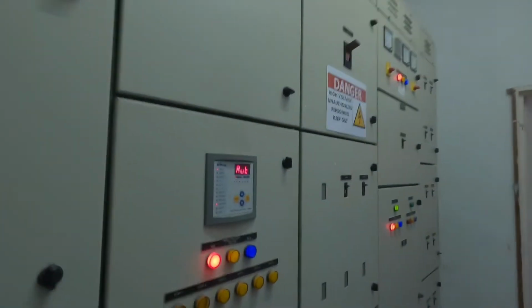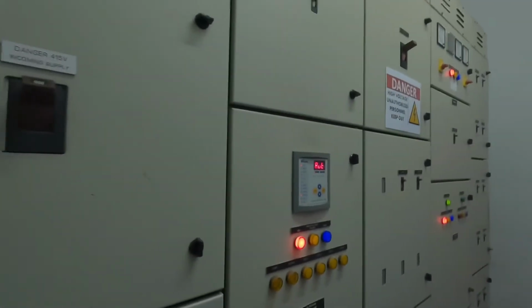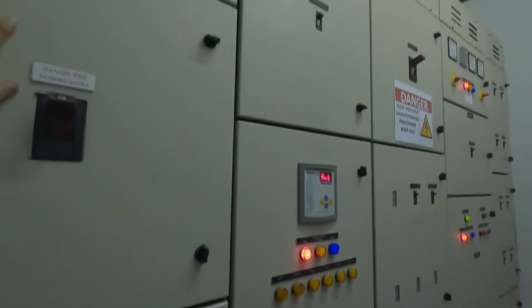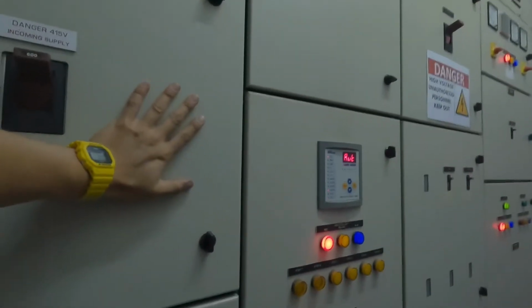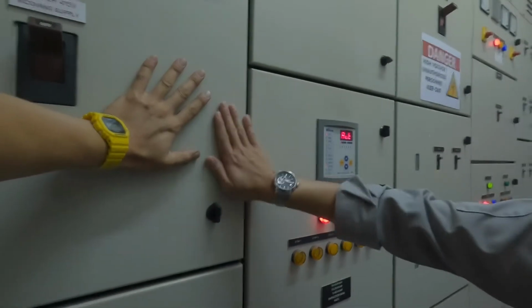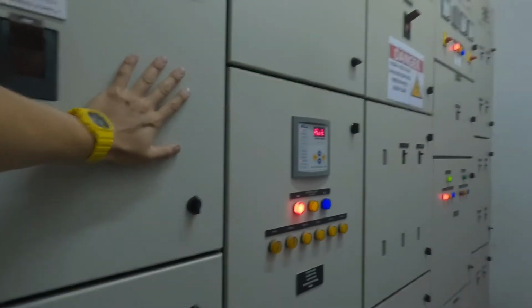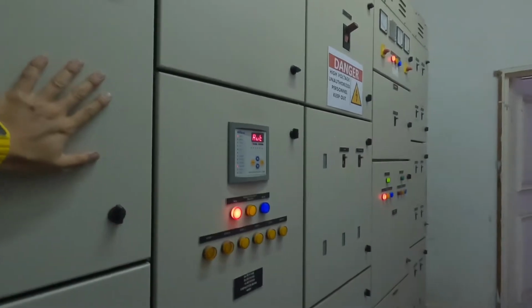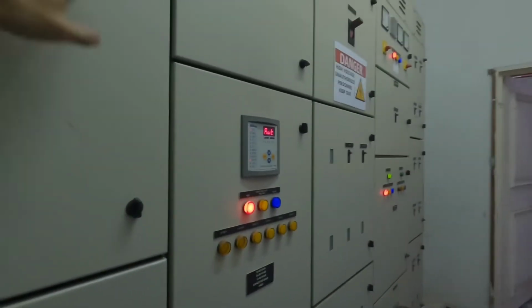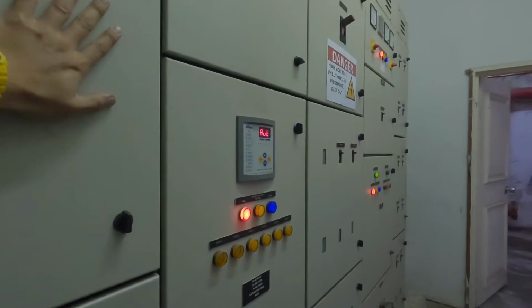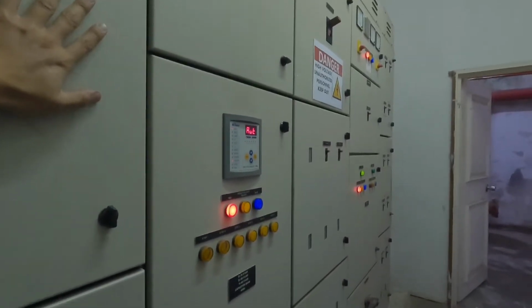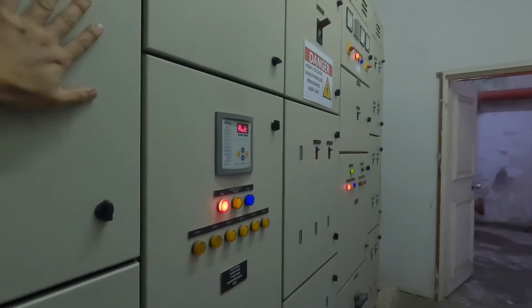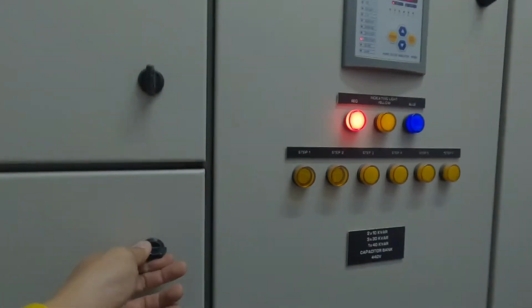Okay, inside this room, because Cameron Highland is cold weather, and this is electrical panel, and now I'm touching this panel, I can tell it's about 15 degrees Celsius. It's not room temperature. And so if let's say this room is exposed to outside air, humidity is quite high and it can cause condensation. So it's advisable to install panel heater. At this moment I need to check whether there's panel heater or not. Okay, this is one thing.